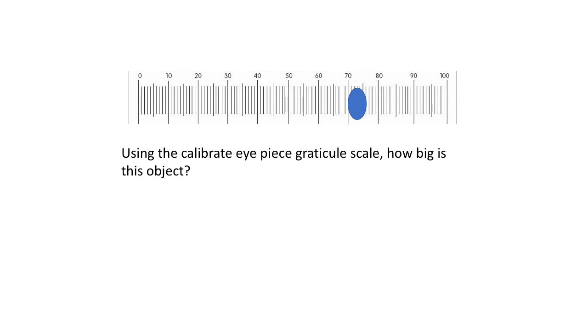Let's look at another example. How big is this object? We've lined it up at 70 and it goes until about 76. We've calibrated and not changed the magnification, so we can stick with our original calibration. One eyepiece graticule scale is equal to 5 micrometers. We've got six divisions, so 6 multiplied by 5 means the width of our object is 30 micrometers.